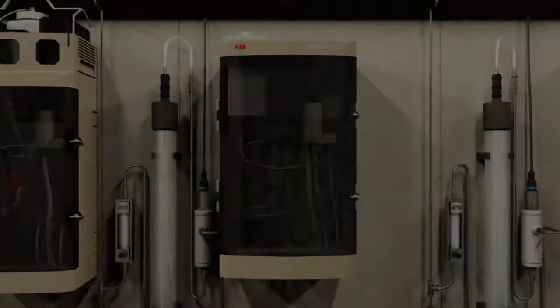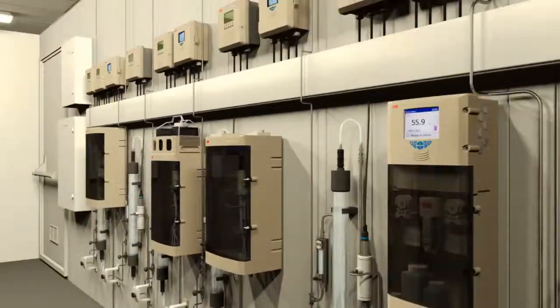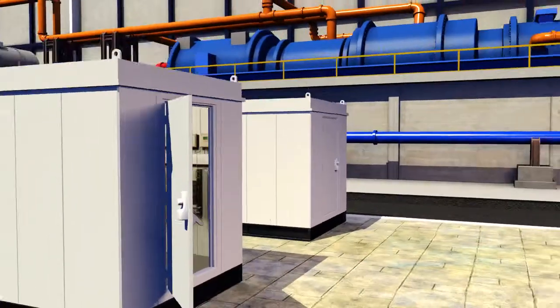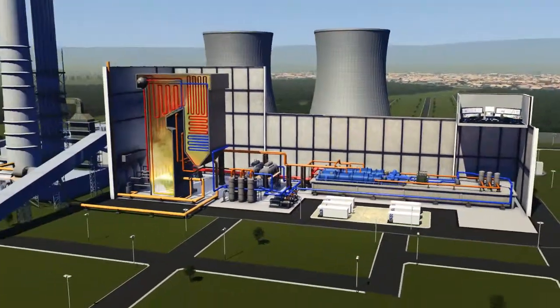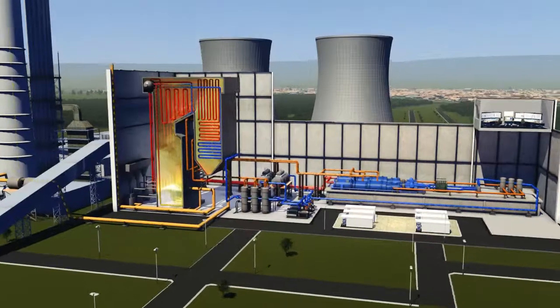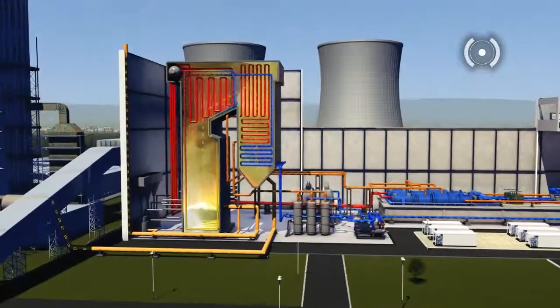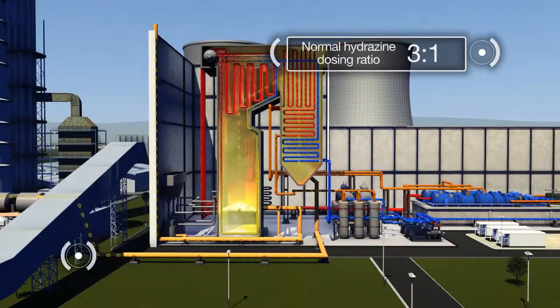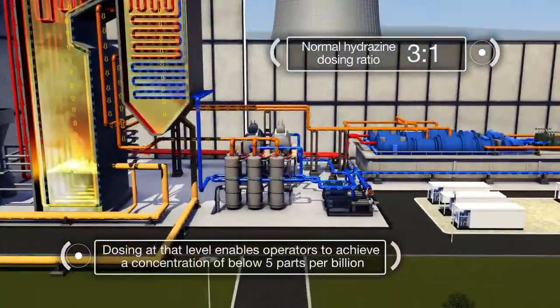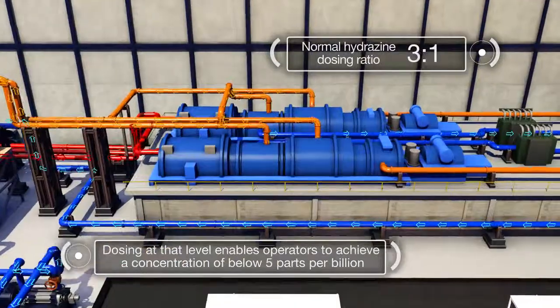Dosing boiler feed water with hydrazine or carbohydrazine can have a major impact on minimizing dissolved oxygen levels. Dosing in a ratio of 3 parts hydrazine to the expected level of dissolved oxygen will enable operators to achieve an acceptable concentration of below 5 parts per billion.